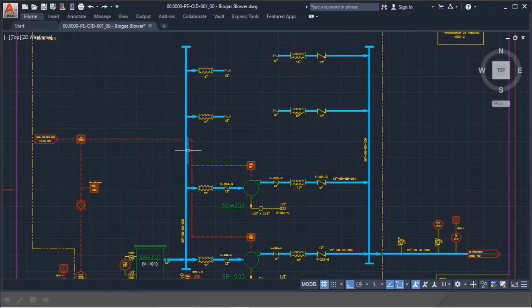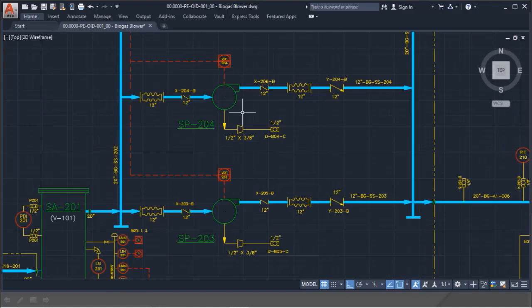However, during the design of the plant, it was already considered the installation of two more blowers because we already have the spares for that. In the bottom of the blower, we have a drain valve. It is very important to open this drain valve during maintenance and before starting the equipment again, because you can accumulate condensate here. There are block valves upstream and downstream of the equipment in order to be able to do maintenance while the other one is still running.